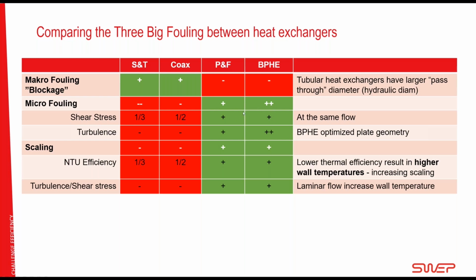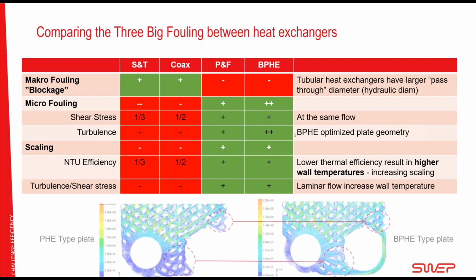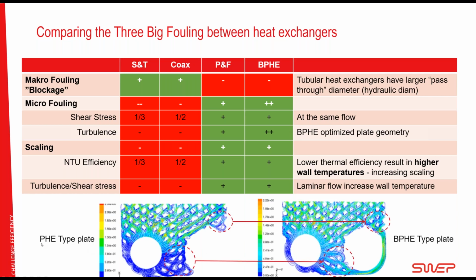So when it comes to the shear stress, the plate and frame and brazed plate are about the same. But when it comes to turbulence and the full flow and no dead areas, the brazed plate, again thanks to this CFD, the BPHE genetics that I spoke about in the beginning. A plate and frame type of plate, since they have gaskets covering one of the connections, one of the port sides here, will have a low flow area in this area and this area that we're able to design away from. So that's why I see the brazed plate as a winner in this one.